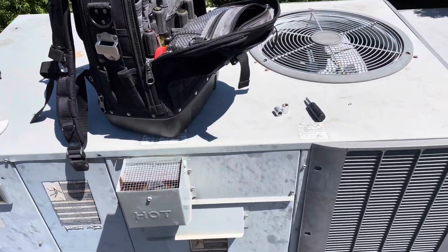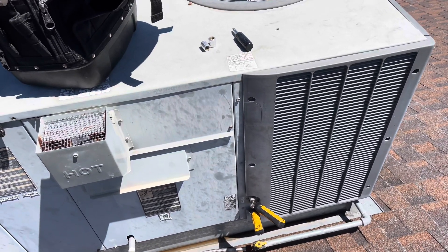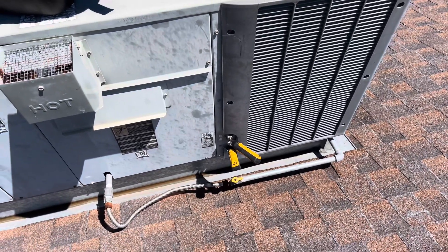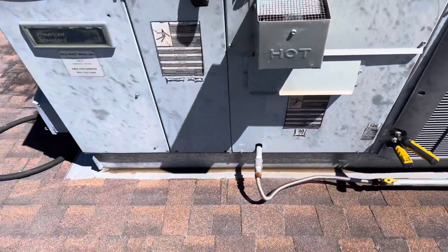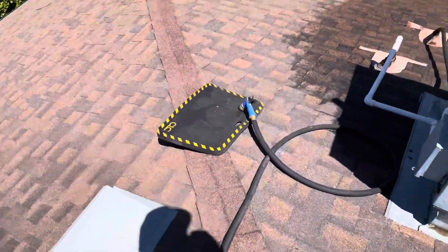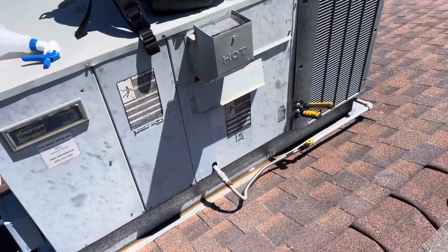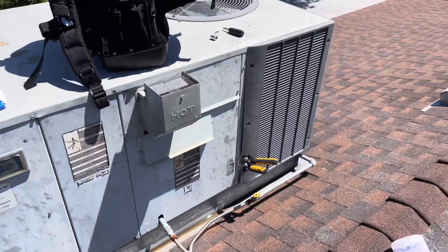I have my digital probe hooked up — I don't know how I'm going to film it on my phone so I took a screenshot and I'll add it to the video. Right now we have 55 over 145: 55 on our low side, 145 on our high side. It's about 70 degrees out here, so those are perfect pressures. This thing is not low on refrigerant and does not need three pounds. It definitely needed an evaporator coil flush, pan cleaning, and condenser coil cleaning — all of which we did today. If you like this video, thumbs up and subscribe. Victory Home Services, a new home service business in Merced, California — hit me up if you're in my area and I hope we can do business. Have a good day everybody.